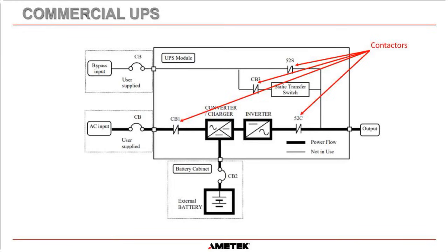And the other thing to notice inside most commercial UPSs is they have circuit breakers and contactors for a lot of their switching. So you can see here, they have a circuit breaker here, but on the output of the system, rather than have a static switch, they have a contactor. So they don't have an inverter static switch. They do have a bypass static switch, but that bypass static switch is only there for instantaneous switching from inverter to bypass or bypass to inverter. Once that initial switching has been done, this contactor here pulls in and basically bypasses the static switch. We'll explain that over the next slide as well.